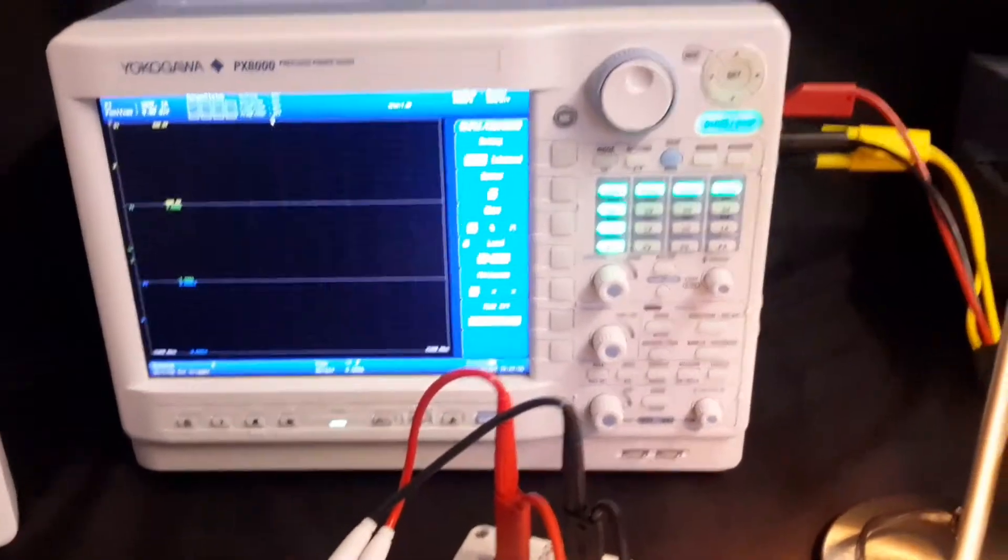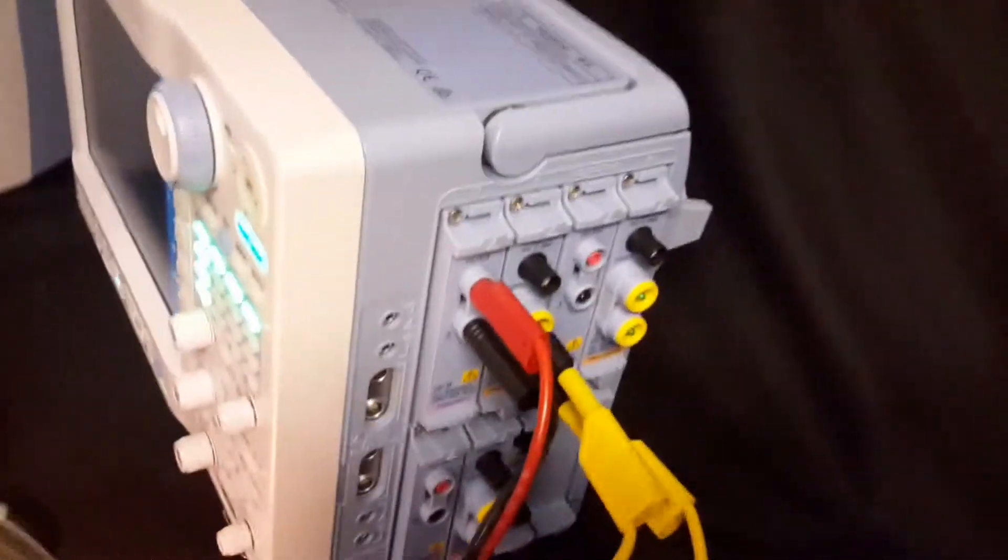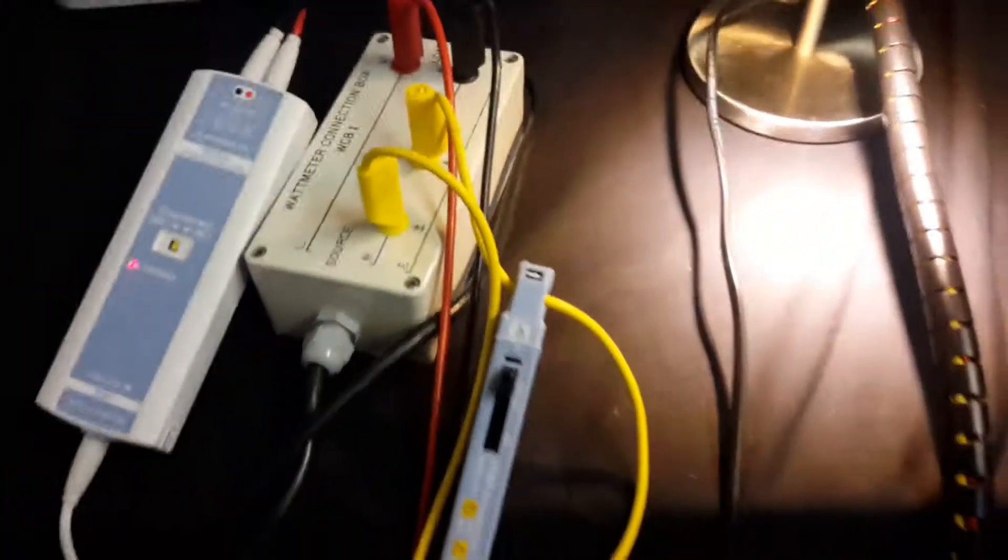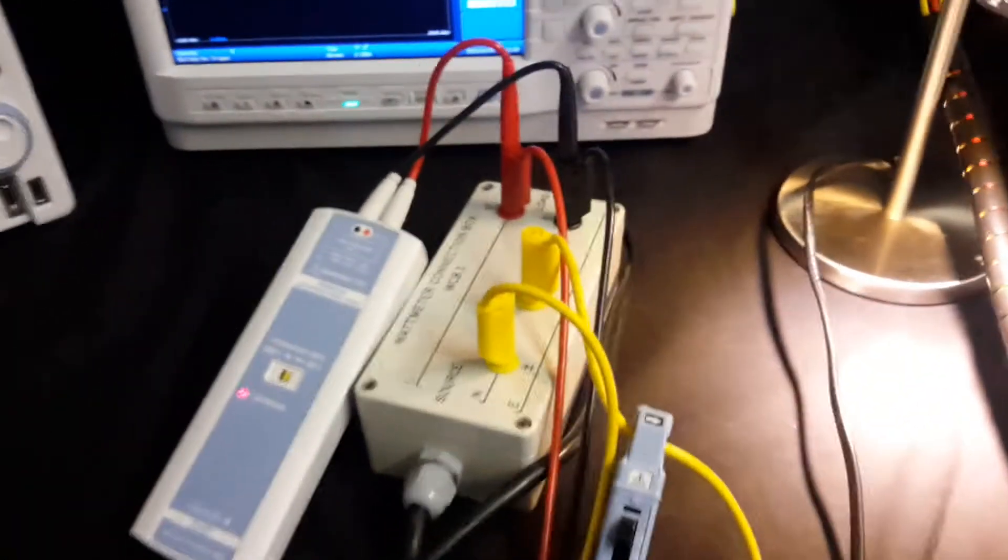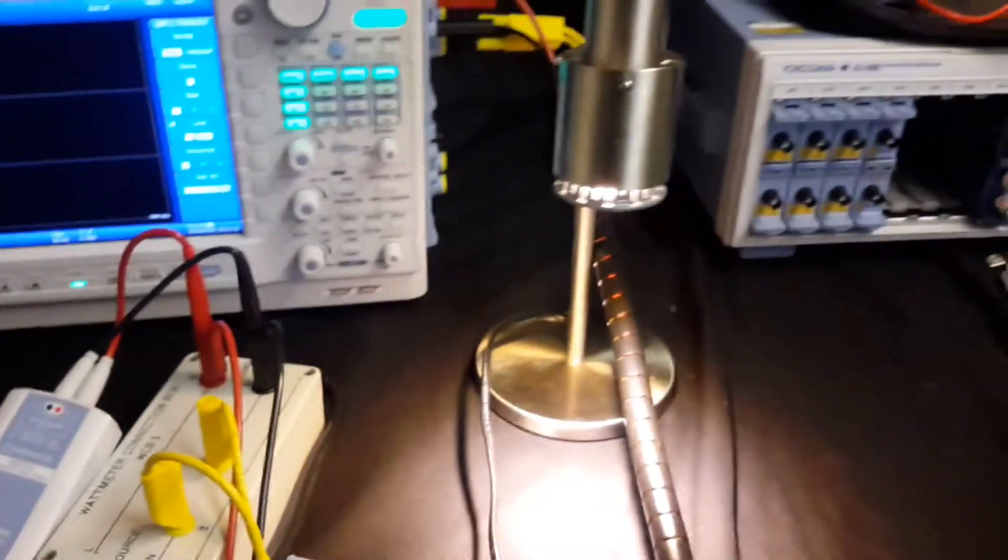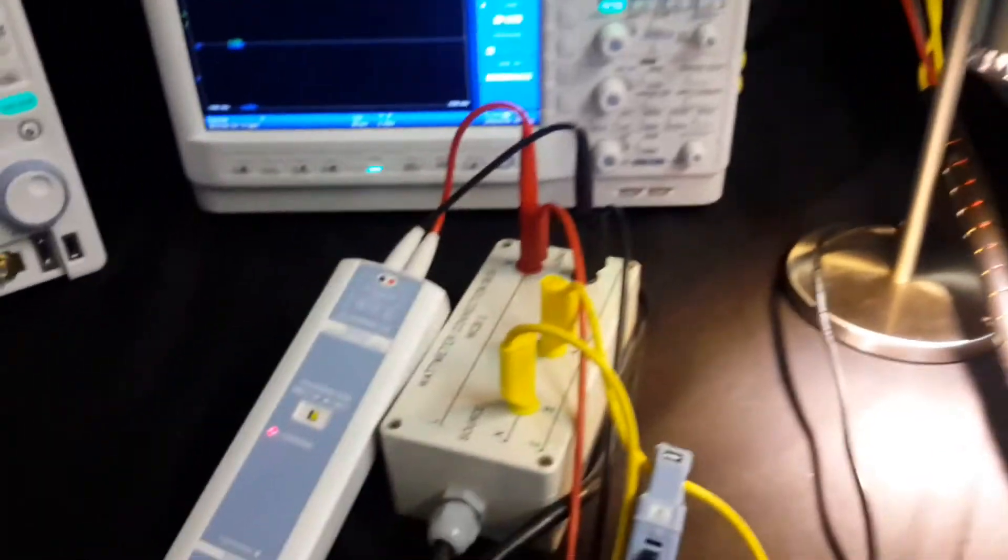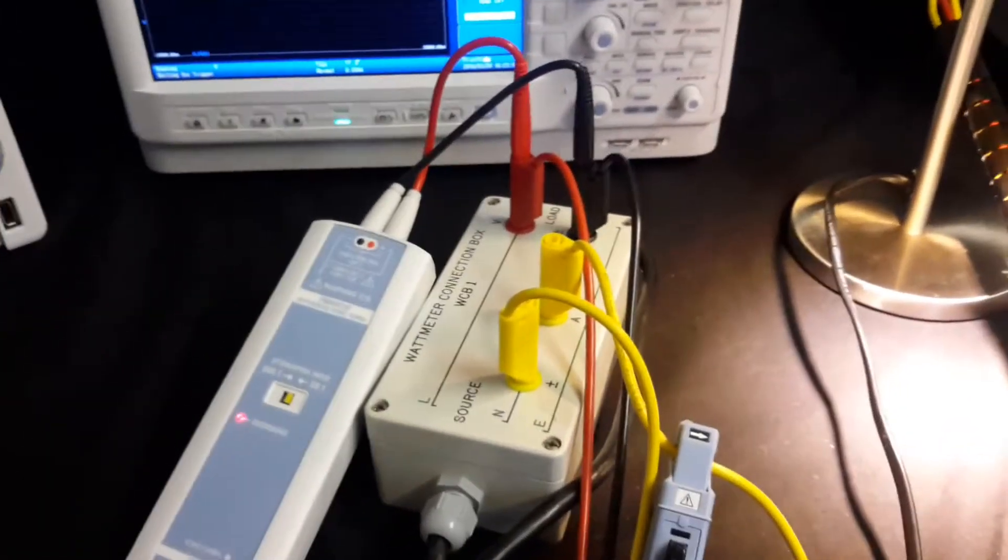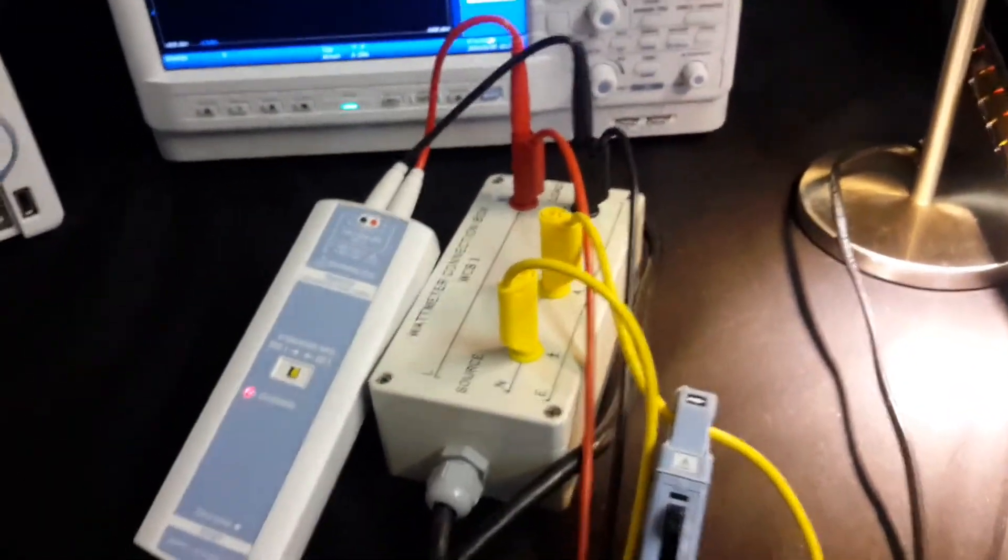The connections on the PX8000, around the side, we have safety banana connectors here for voltage. We also have safety banana female connectors for the current as well, and these go around to the breakout box. So we're measuring the same product, measuring the same parameters at the same time.